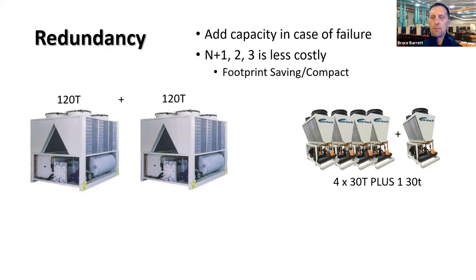In this example, I've got four 30-ton modules to build my 120-ton chiller. I've got an extra 30-ton module for redundancy that would stack into that array. You could add two modules, three modules, four modules. So we're not counting on catastrophic failure for the entirety of that bank. Maybe just one module, one flow switch, et cetera. Talk a little bit more about that. When you talk about total installed cost, a modular machine is going to be higher priced, but there's less installed cost given the footprint, wiring, et cetera.